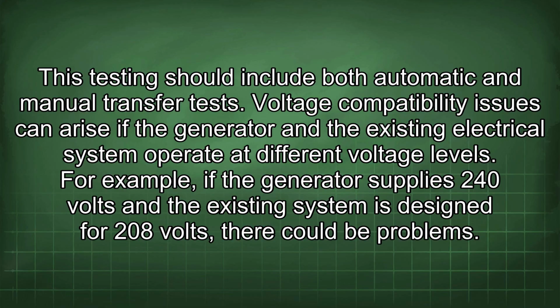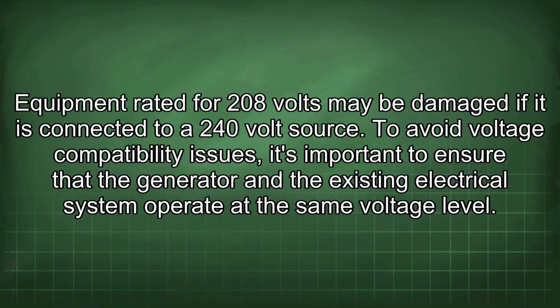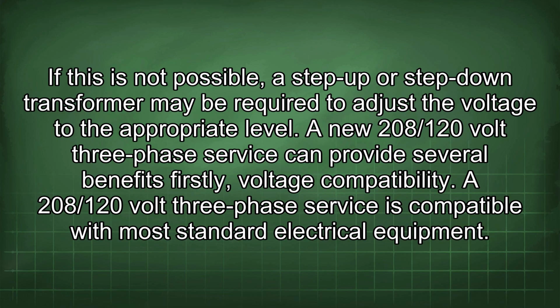Voltage compatibility issues can arise if the generator and the existing electrical system operate at different voltage levels. For example, if the generator supplies 240 volts and the existing system is designed for 208 volts, there could be problems. Equipment rated for 208 volts may be damaged if it is connected to a 240 volt source. To avoid voltage compatibility issues, it's important to ensure that the generator and the existing electrical system operate at the same voltage level. If this is not possible, a step-up or step-down transformer may be required to adjust the voltage to the appropriate level.